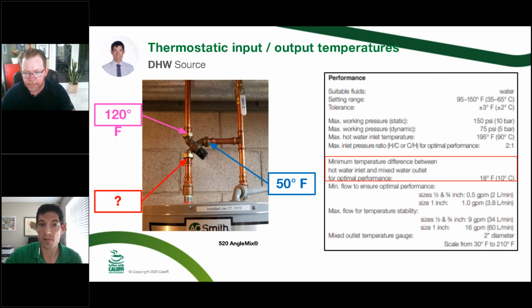So mixing valves are going to publish that minimum temperature difference between hot and mixed outlet. It applies more to thermostatics, and I'll talk about that a little bit later, than the Legio mix, which is an electronic ball. But you can't have a mixed set point of 120 and have the same set point at your water heater. You're going to lose those 18 degrees, and you're going to have taps that are colder than you had expected, because you are mixing some of that cold water, and that's why you need to set it hotter. But the good news is, and I think that you've had a lot of experience with this too, Michael, is that you can make that water heater seem like a bigger water heater if you store it warmer too. So that can be helpful in the selection of these components too.